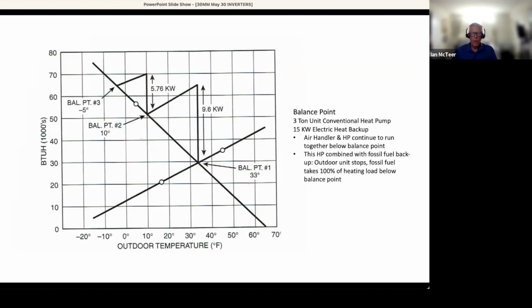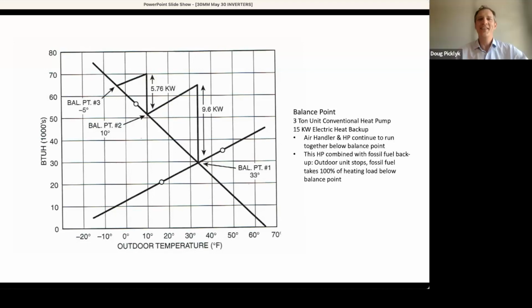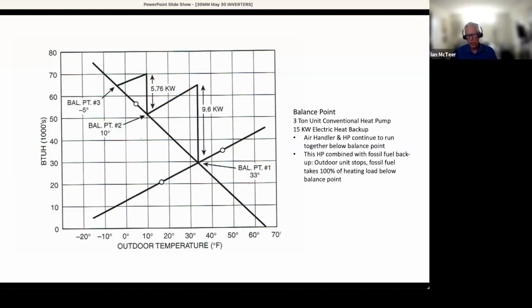So, I mean, this is the cold climate heat pump is decidedly going to outperform this old blister. Right. So at the first balance point, you're going to get 9.6 kilowatts, roughly 10 kilowatts of electric heat to come on. That slope is then going to parallel the original slope until you hit the second balance point at 10 Fahrenheit, at which point an outdoor thermostat will bring on the last 5 or 6 kilowatts of electric heat. And that's the third balance point at -5 Fahrenheit there in this elderly drawing.